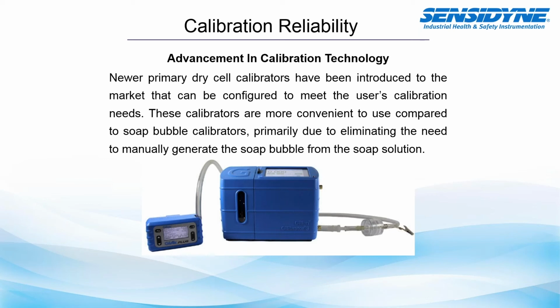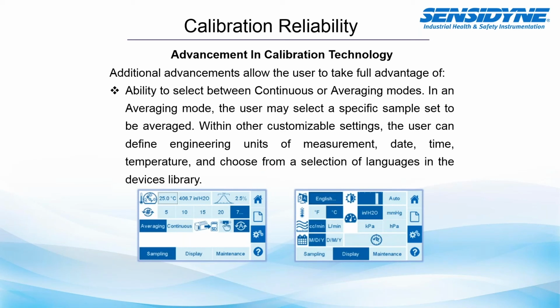As you can imagine, if you've used some of the older devices, having to generate soap bubbles for each sample is both time-consuming and, again, can be disrupted if the soap bubbles pop or if you have multiple soap bubbles that are generated with a single depression. Additional advancements allow the user to take full advantage of the ability to select between continuous or averaging modes. In averaging mode, the user may select a specific sample set to be averaged. Within other customizable settings, the user can define engineering units of measurement, date, time, temperature, and choose from a selection of languages in the device library. So with the technology advancements, you can really customize both what your user settings are and what your user output should look like.